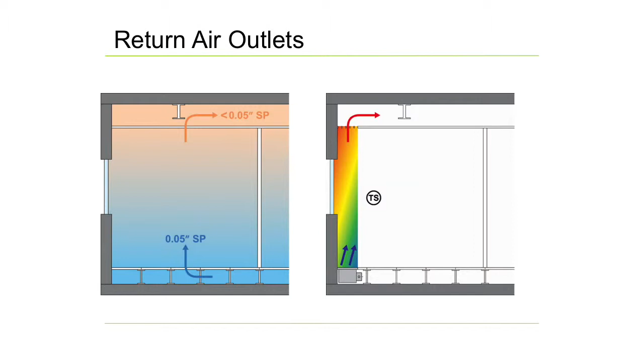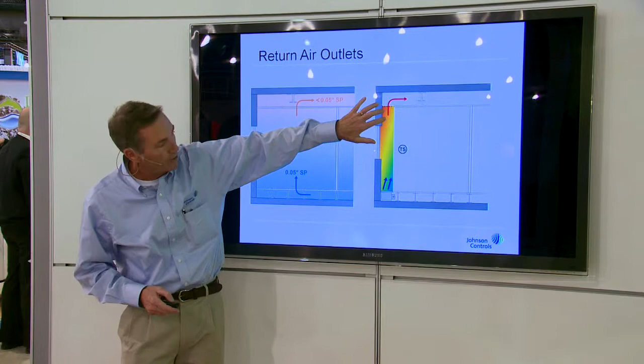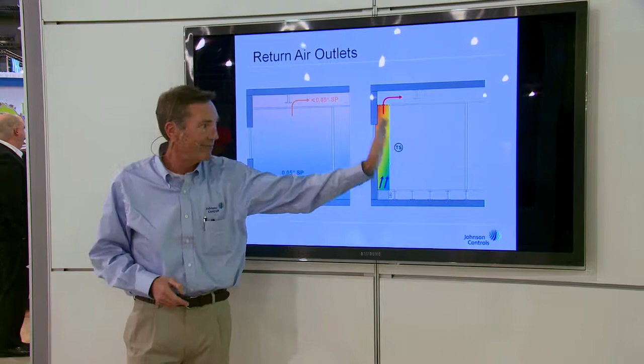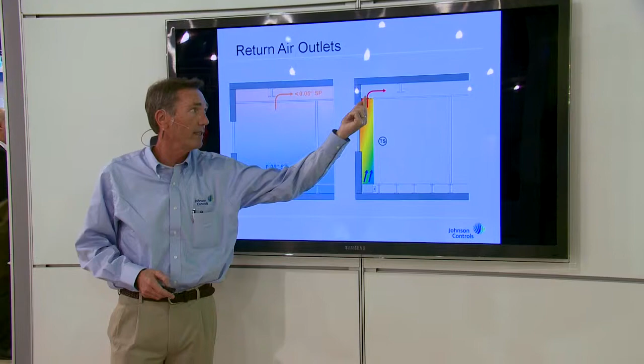This shows how we'd normally do it: you want your return grills close to the perimeter, as high as you can get them, so we're getting it up and out versus getting it mixed into the space. That's visually what we're trying to do—keep them up high, or put a larger return air grill, or pull the ceiling back from the perimeter wall, leaving a gap, which helps us too.